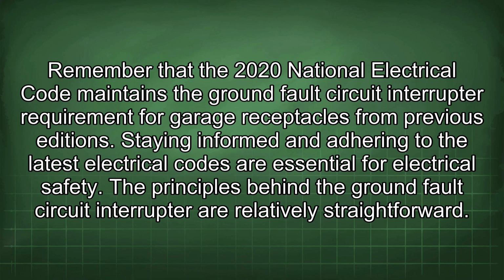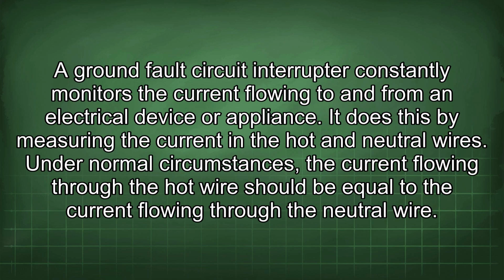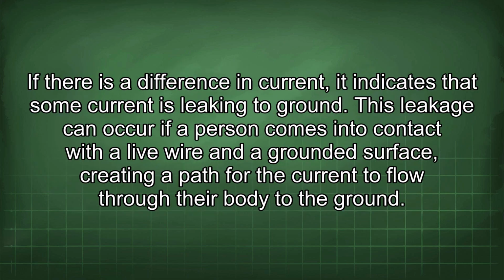The principles behind the ground fault circuit interrupter are relatively straightforward. A ground fault circuit interrupter constantly monitors the current flowing to and from an electrical device or appliance. It does this by measuring the current in the hot and neutral wires. Under normal circumstances, the current flowing through the hot wire should be equal to the current flowing through the neutral wire. If there is a difference in current, it indicates that some current is leaking to ground. This leakage can occur if a person comes into contact with a live wire and a grounded surface, creating a path for the current to flow through their body to the ground.